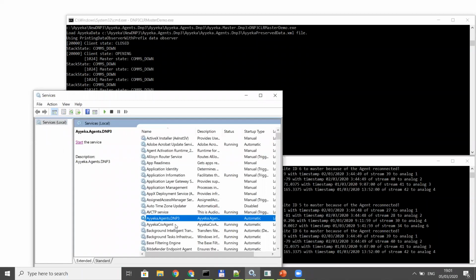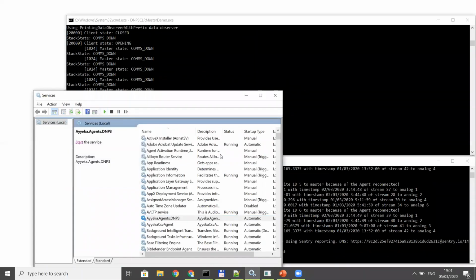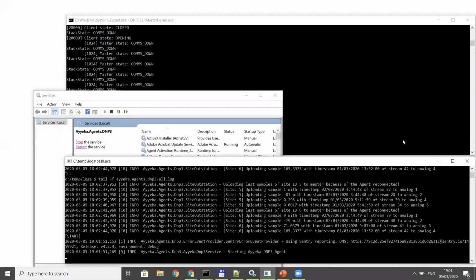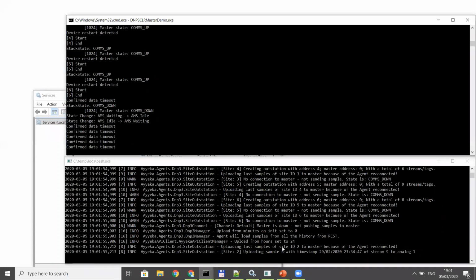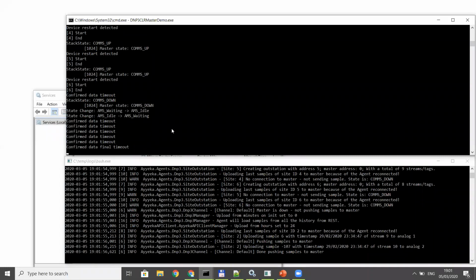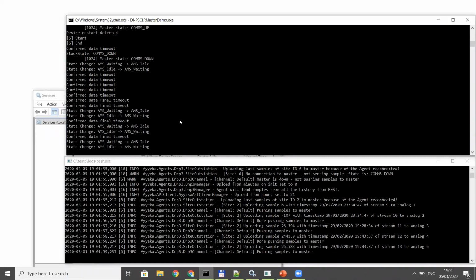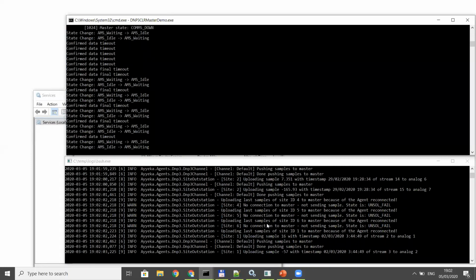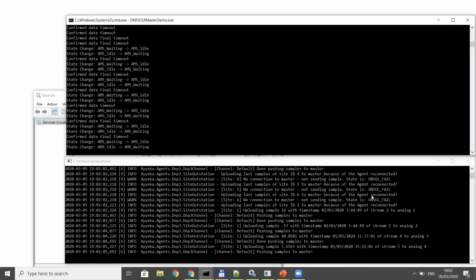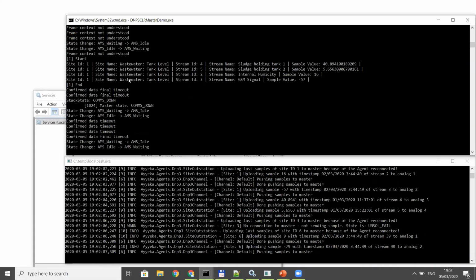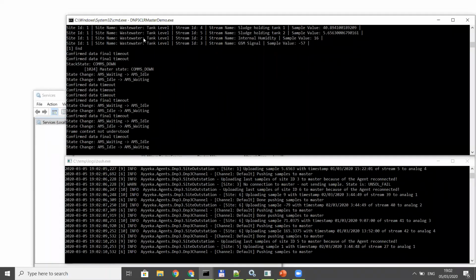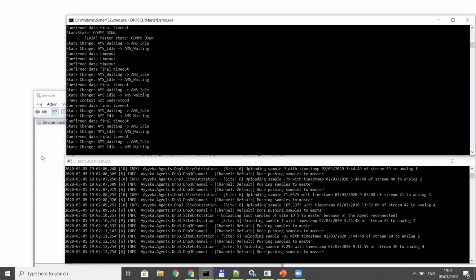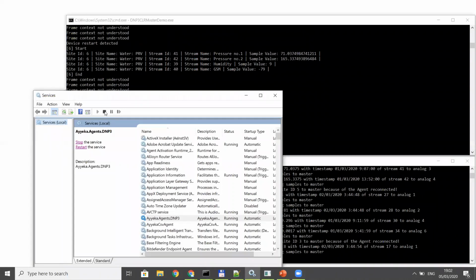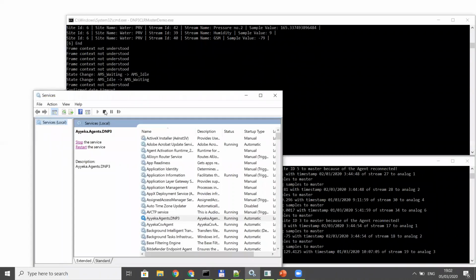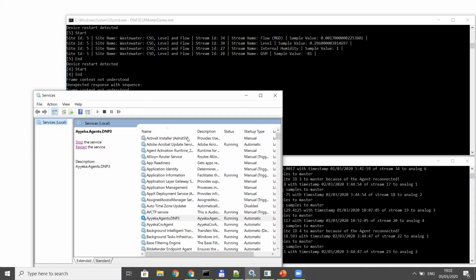So I'm going to click on our agent, here's our Ayyeka DNP3 agent, we're going to hit play. You can see it came alive over here in the bottom part of the screen, and you can see what the SCADA system is reading on the top part of the screen. So it's starting to send unsolicited data, and it's initially failing, but here you can start to see that it actually got some values coming through, and you can see the metadata is coming through with the last values. Let me just stop it here so we can take a quick look in terms of what the SCADA system is seeing.